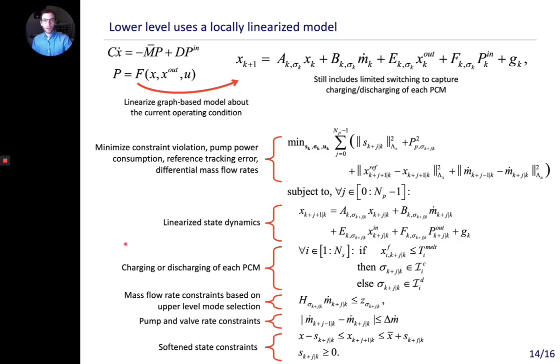So what we do here is we linearize locally about the current operating condition, with the exception that we include models both for charging and discharging of each PCM, so that if our temperature gradients flip, our model will be accurate. We found that this approximation of the dynamics gives sufficient accuracy over the horizon of this lower level controller to allow us to make good decisions about how to govern our system, how to move thermal energy around, and choose actuators.